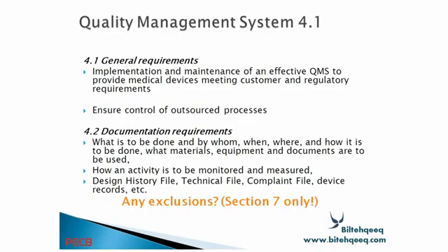And 4.2, documentation requirements: what is to be done and by whom, when, where and how it is to be done, what materials, equipment and documents are to be used, how an activity is to be monitored and measured, design history file, technical file, complaint file, device record, and any exclusion. If there is any exclusion, we have to also describe this exclusion. So we have to develop proper documentation procedures, who is responsible for what and who is doing what.